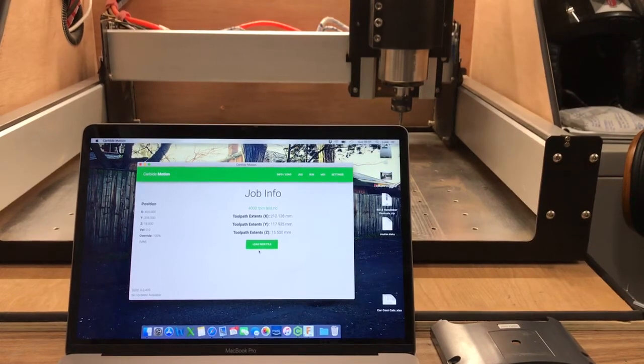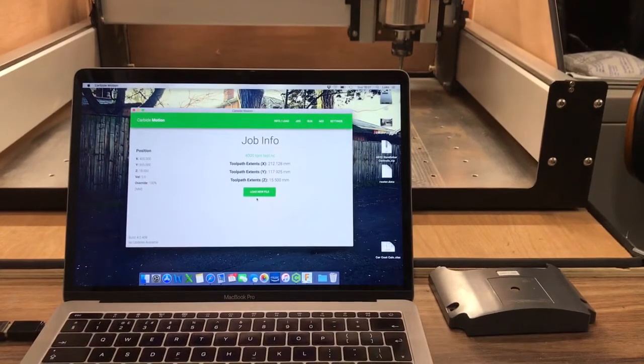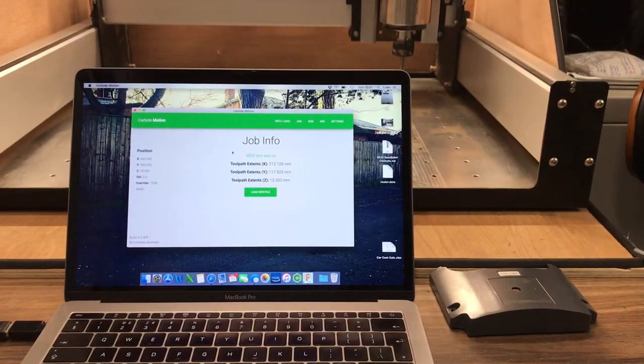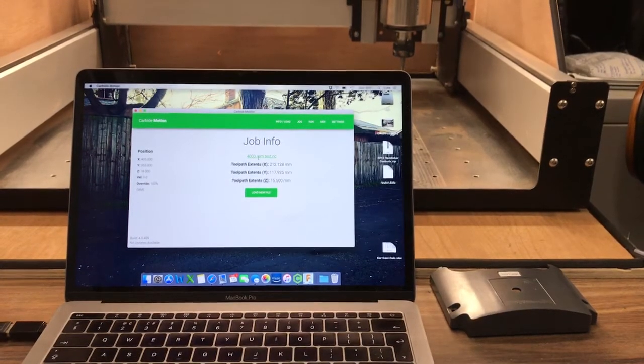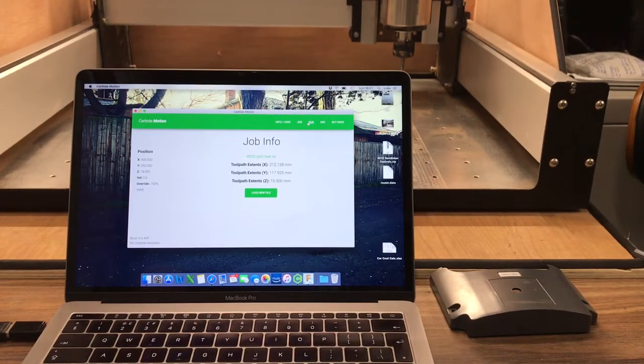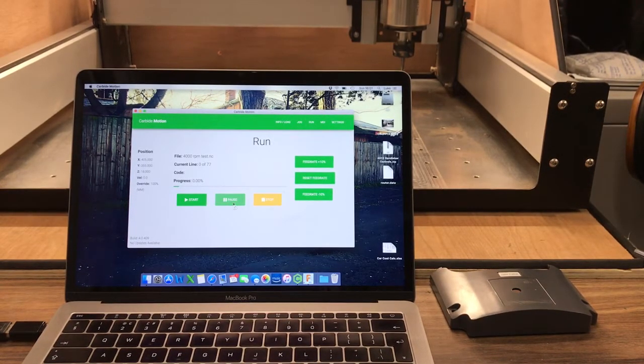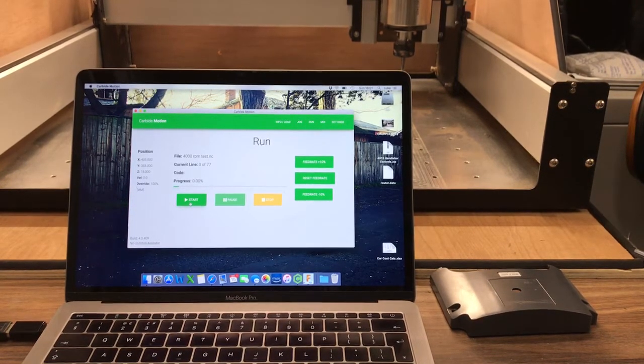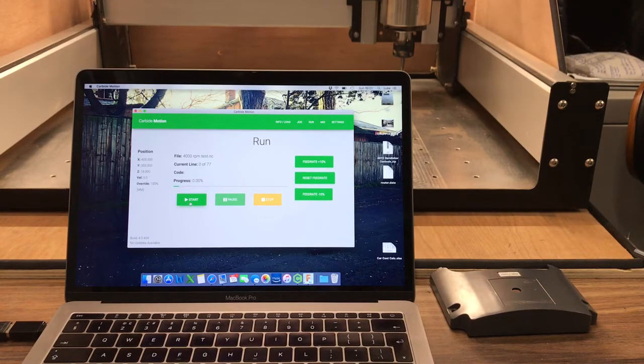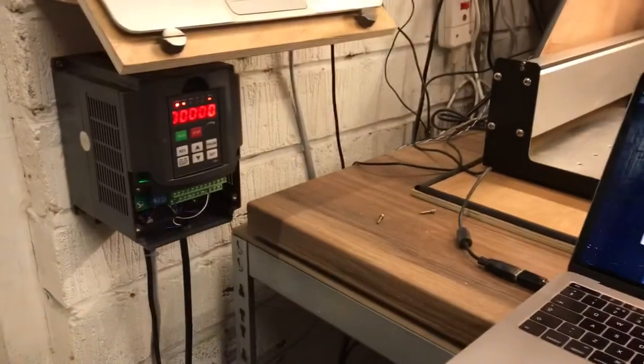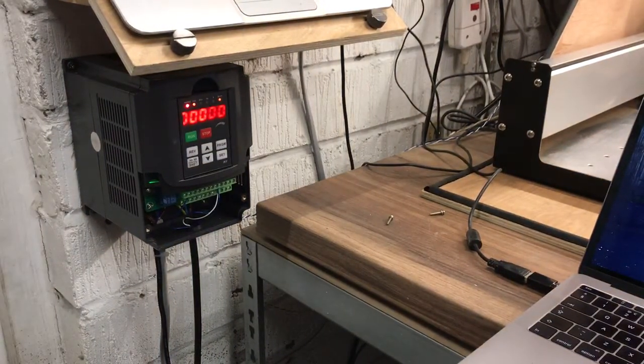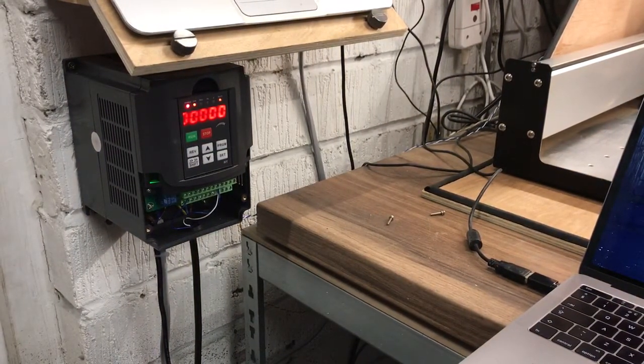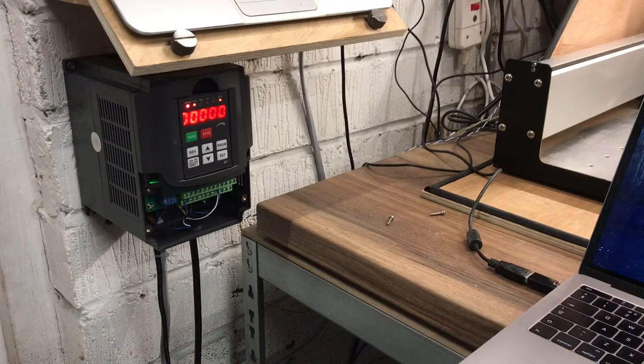Now I've got a couple of files here. I've got a 4000 RPM test which I've just knocked together very quickly. I'll click on run on that and click start. What's gonna happen now is the router's gonna start up and we're gonna see the VFD accelerate to around about 4000 RPM.